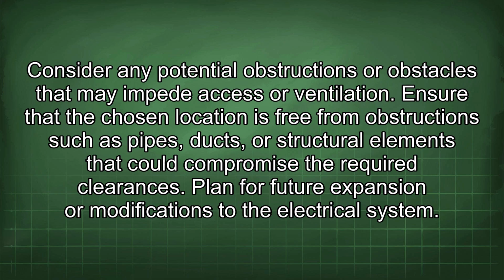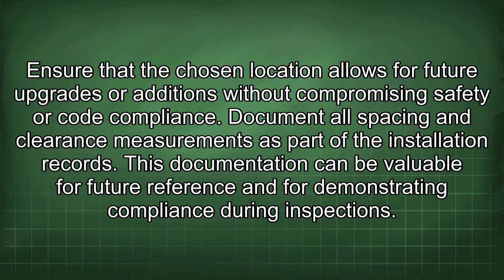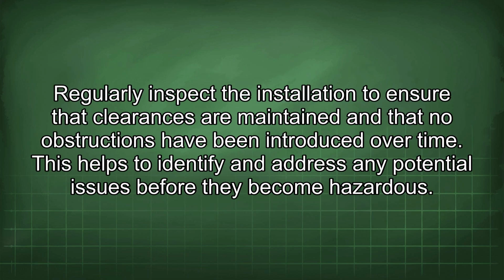Consider any potential obstructions or obstacles that may impede access or ventilation. Ensure that the chosen location is free from obstructions such as pipes, ducts, or structural elements that could compromise the required clearances. Plan for future expansion or modifications to the electrical system. Ensure that the chosen location allows for future upgrades or additions without compromising safety or code compliance. Document all spacing and clearance measurements as part of the installation records. This documentation can be valuable for future reference and for demonstrating compliance during inspections. Regularly inspect the installation to ensure that clearances are maintained and that no obstructions have been introduced over time. This helps to identify and address any potential issues before they become hazardous.